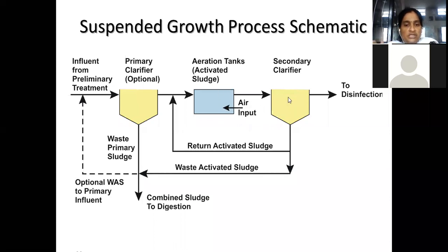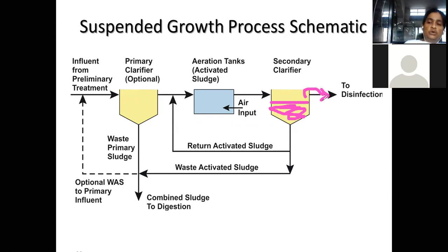That entire waste, along with solid and liquid, will be sent towards the secondary clarifier. Here we are providing the sedimentation process. The sludge that has been consumed by the microorganisms will settle down at the bottom of this clarifier.